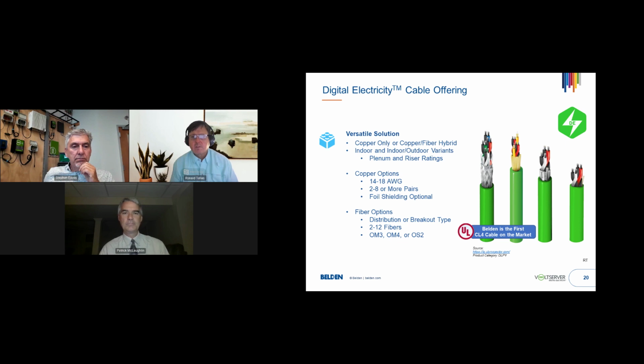Yeah, so the construction you just described is what's called a hybrid cable, the second one from the left. It shows copper conductors for the fault managed power, the digital electricity power circuit, and then the yellow is the fiber, which delivers the data to the end device. You'd have to strip back the cable, expose those, splice on connectors, and then have the copper conductors go into the screw terminals typically, and that's how it would be used. So yes, you can have both under one cable sheath.